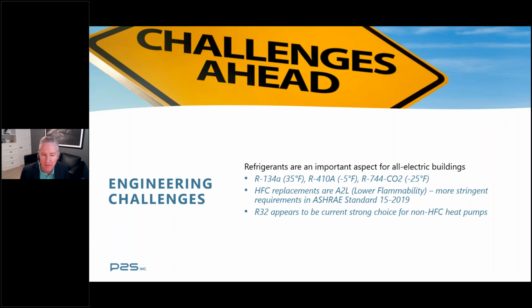CO2 is not an HFC. And HFC replacements, in many cases, like California, we're starting to see things being phased out. So we're going to have to move to replacements that are A2L, a lower flammability category. We were all dealing with no flammability on the HFCs, and that changes to more stringent requirements in the new ASHRAE Standard 15. Keep those things in mind when we're doing that.